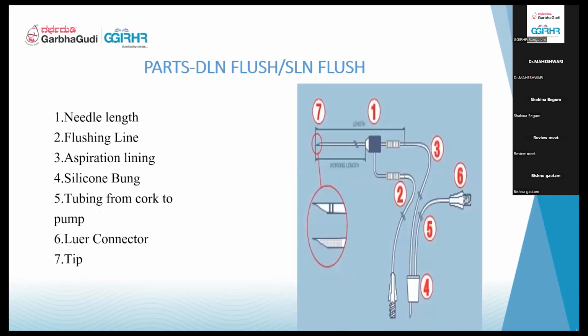So what is the difference with the double lumen or the flushing needle? The needle that you can see here has got 2 lumens, hence it is called the double lumen. One is for aspiration, one is for flushing. The flushing lumen gets connected to the extra tube here, through which you can flush fluid, so that flushing will be possible. You can flush the entire follicular fluid.